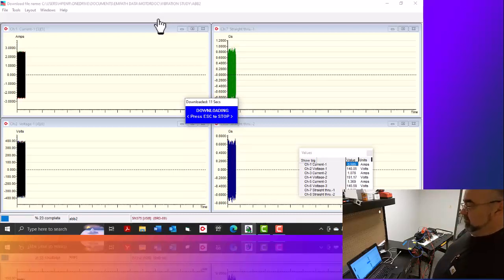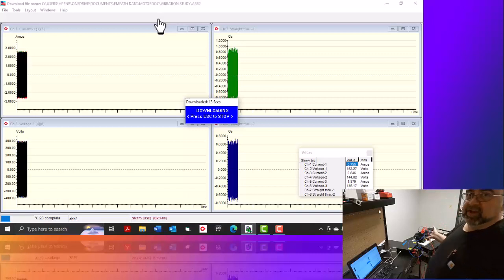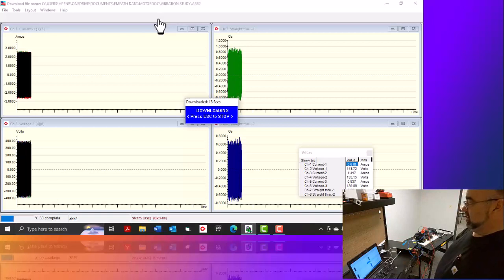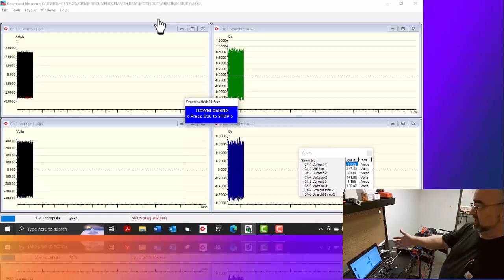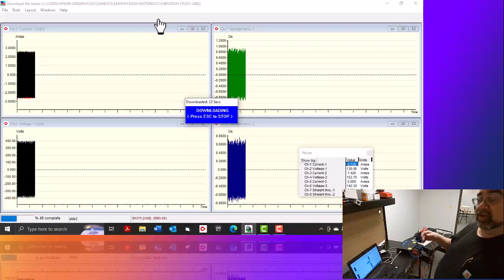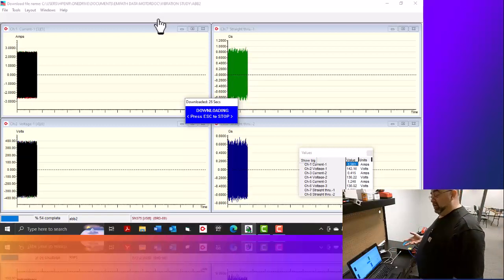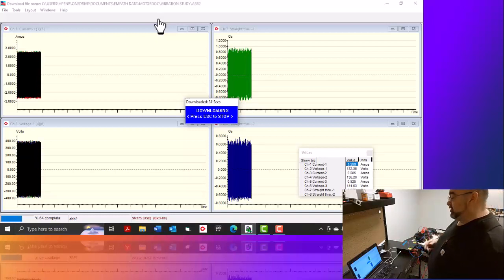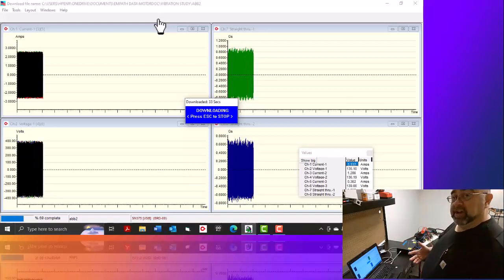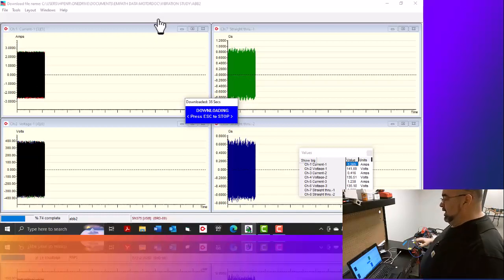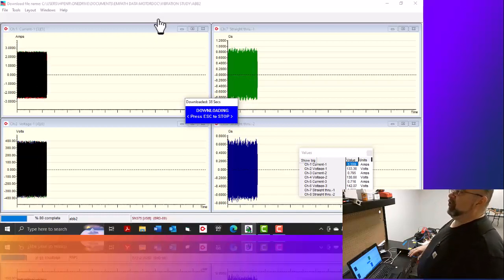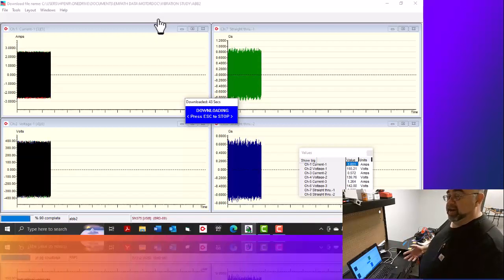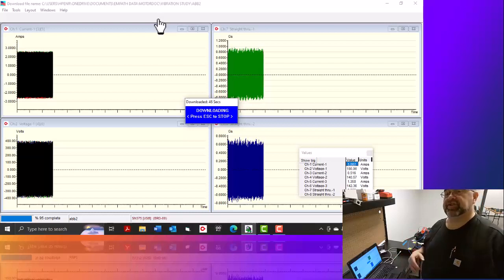So for instance, how many hours is this operating, so we can calculate kilowatt hours and automatically detect some of the other conditions. So while we're watching, I'm seeing what's going on as far as G's and everything else. Now though, unlike the last time, I'm actually going to be able to change the acceleration over to velocity when I'm doing my spectral analysis. Primary difference is for some faults, it's not going to automatically detect the vibration faults. You have to do some of that analysis on your own, but the calculations are called up.